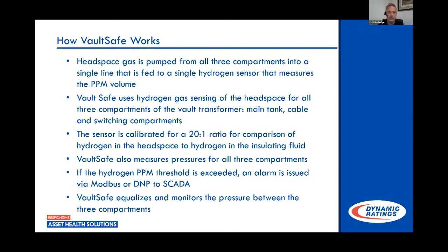So by pressurizing this compartment with the rest of the compartments with our system, now we're able to detect leaks, and that's done by setting an alarm similar to what you would do with a substation. You should have about a pound of pressure on the transformer during normal operation. And so we can set alarm points at a quarter pound, a half a pound. When the pressure drops down to that level, you can get an alarm into your SCADA, and then you're pretty aware that, hey, we have a leak occurring somewhere on this transformer. Go out and do your maintenance at that point.